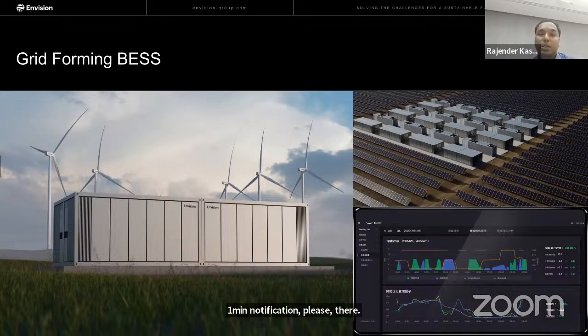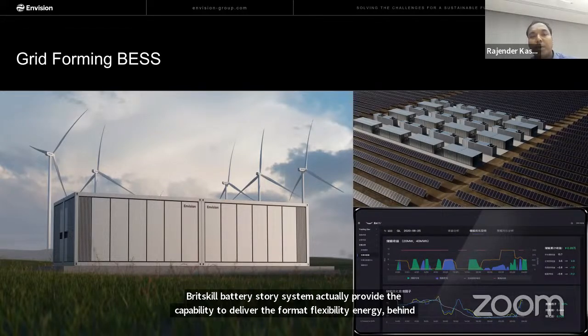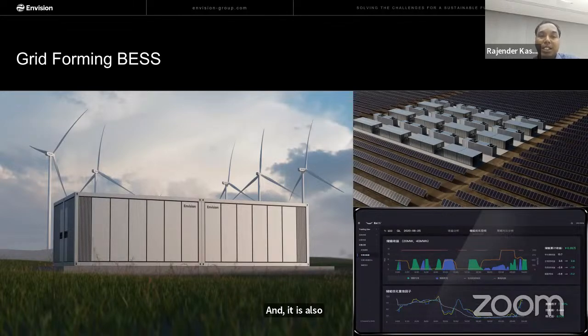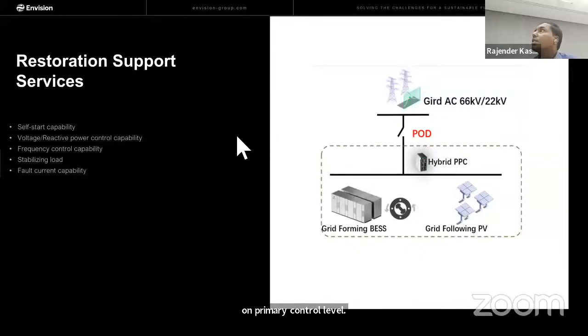The grid scale battery storage system provides the capability to deliver firm and flexible energy behind the inverter. The grid forming BESS also regulates the frequency in the microgrid, provides synthetic inertia, and acts as a frequency governor in droop mode at the primary control level. And to solve the problem of the restoration service, given the recent adverse weather conditions in this MENA region: in the restoration sequence of a power system, the larger generating unit is switched on first, and later the network or transmission system is energized. While doing this, the grid forming inverter, being a voltage controlled source, will not rely on the PLL loop, and is capable of generating its own voltage reference.